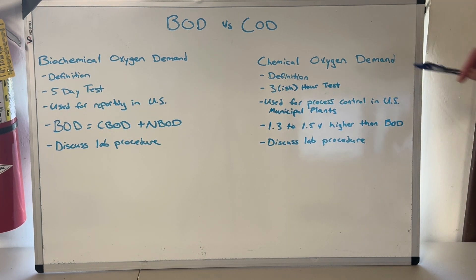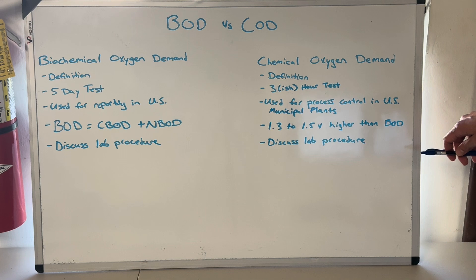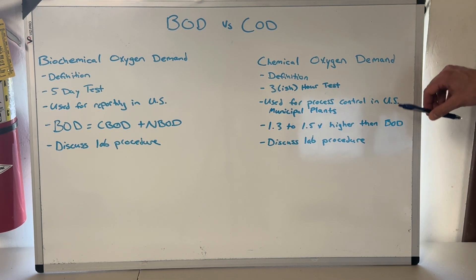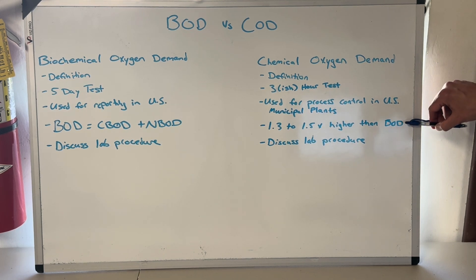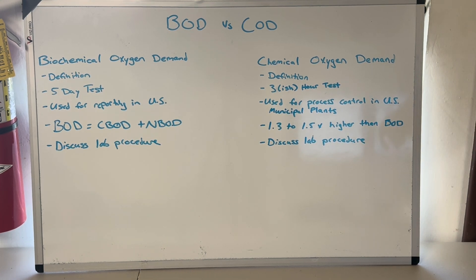As a quick example: say your target BOD for your effluent is 10 milligrams per liter for a municipal waste treatment plant. If you do a COD test and it comes back at 10 mg/L, you're actually lower than your target theoretically — that's fine. But if that COD test comes back at 30 mg/L, you might have a problem. It's just a trigger to say, 'Hey, look closer,' and catch the issue before it really becomes a problem.